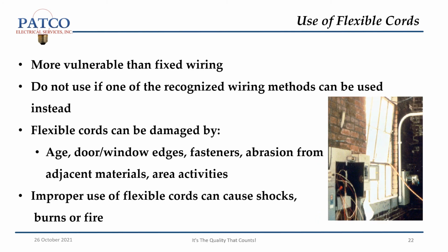Use of flexible cords. They are more vulnerable than fixed wire. Do not use them if one of the recognized wiring methods can be used instead. Flexible cords can be damaged by age, door and window edges, fasteners, abrasion from adjacent materials, and area activities. Improper use of flexible cords can cause shocks, burns, or fire.